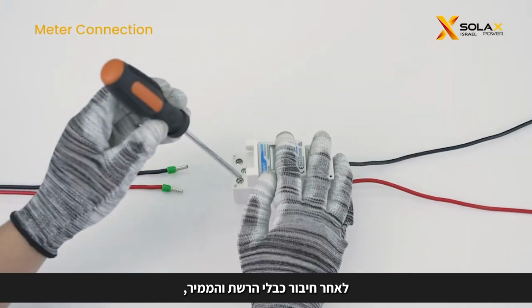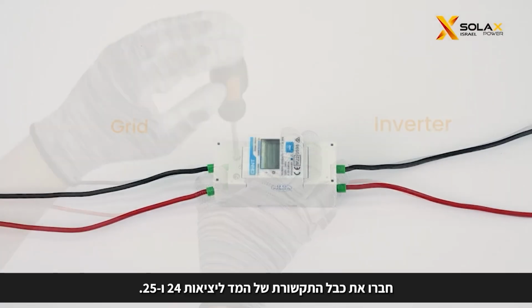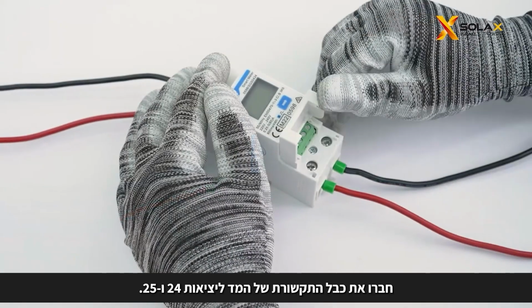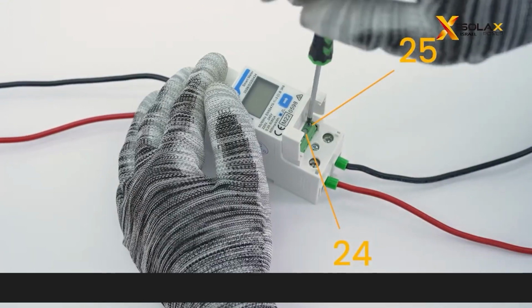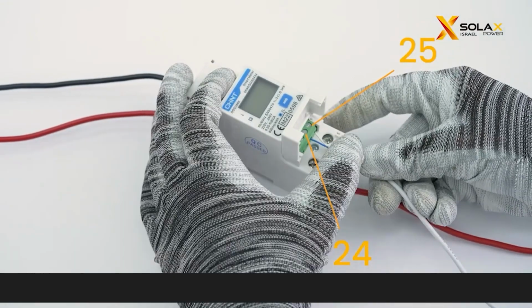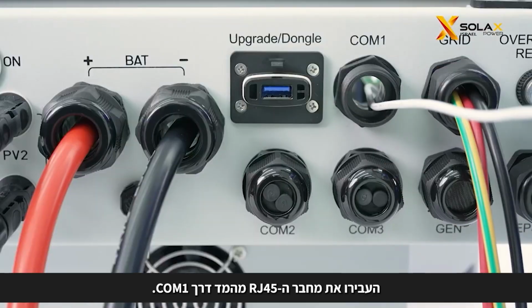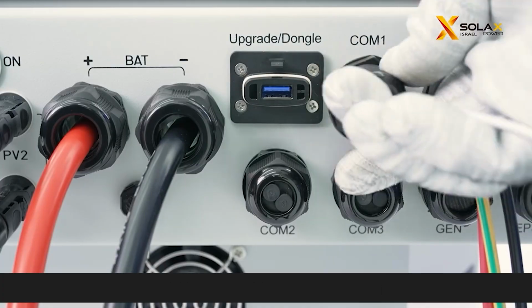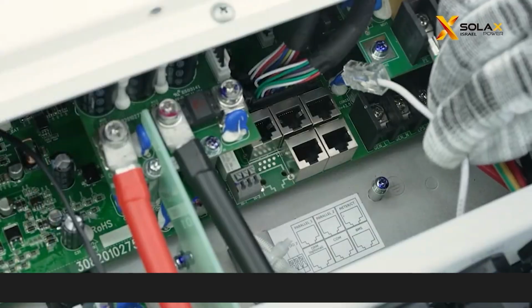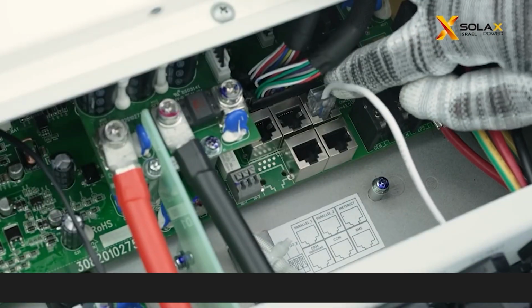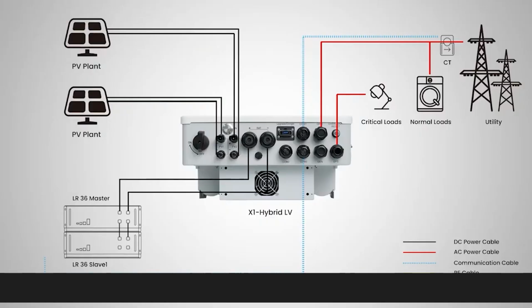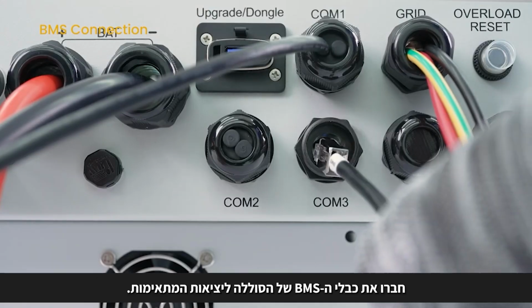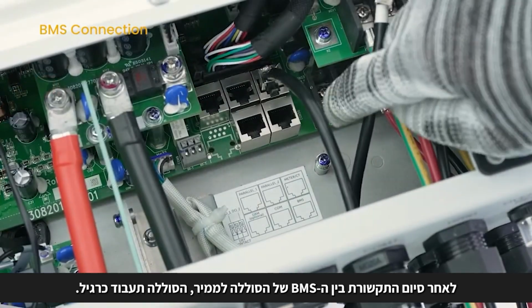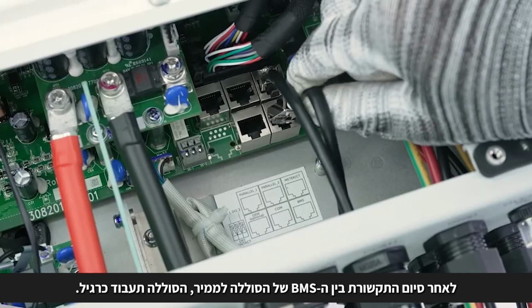After connecting the grid and inverter cables, insert the communication cable of the meter into the 24 and 25 communication ports. Pass the RJ45 connector from the meter through COM1. Insert the battery BMS cables into the corresponding ports. After the BMS communication between the battery and the inverter is finished, the battery will work normally.